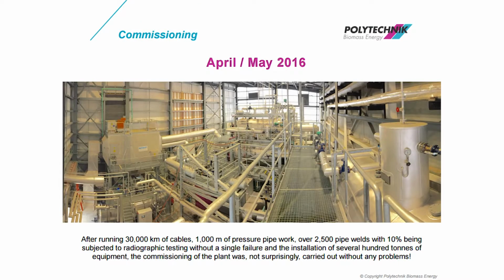So this photo here is taken around commissioning. You can see here we've got the top of the deaerator here, electrostatic precipitator here, diesel boiler down in here, 2 megawatt biomass boiler here, and the 4 megs up the back. So there's approximately 30 kilometres of cable on the job. It's about a kilometre of pressure pipe work, 2,500 pressure pipe welds, subjected to 10% radiography. And under the contract, if we had a weld fail radiography, we had to do 100%. So it was really important that the quality was managed well.